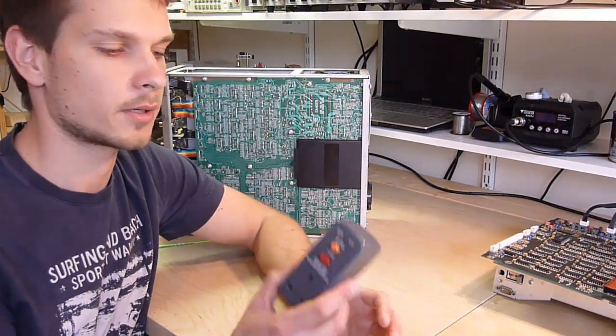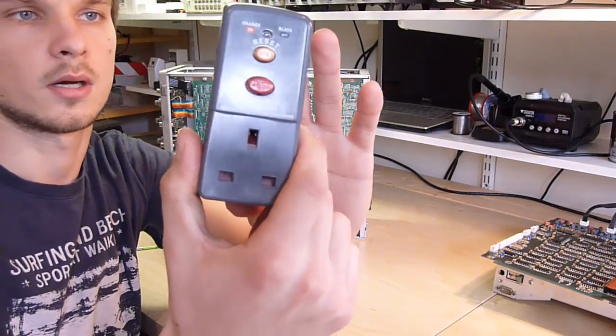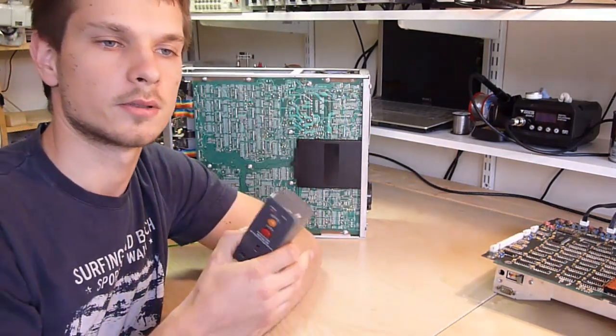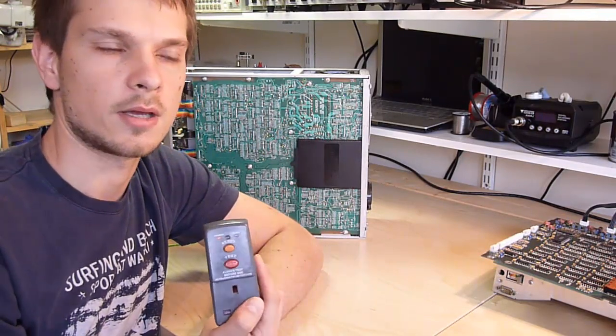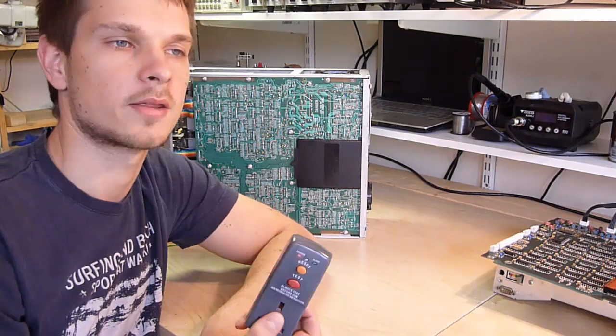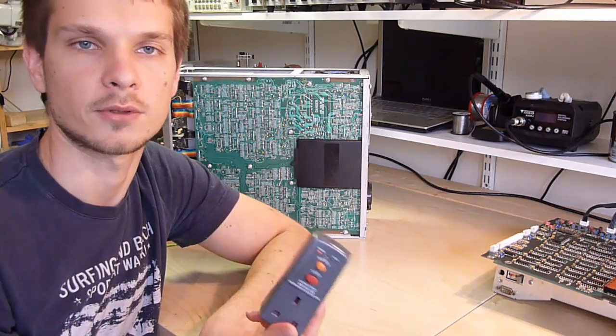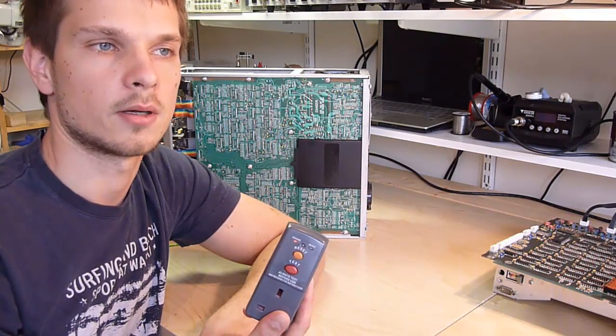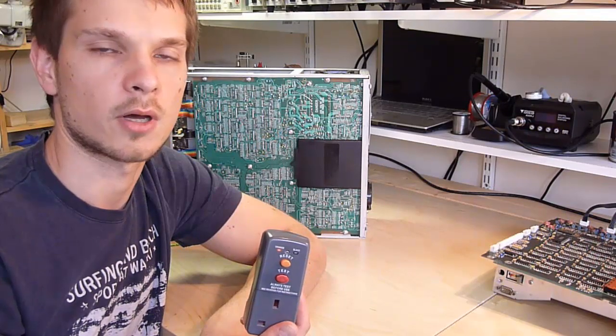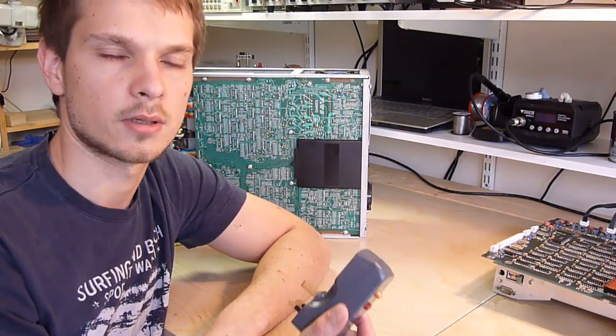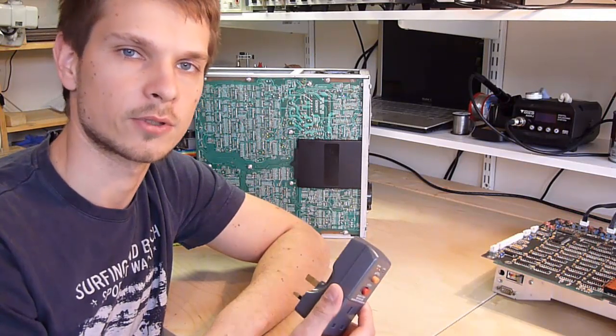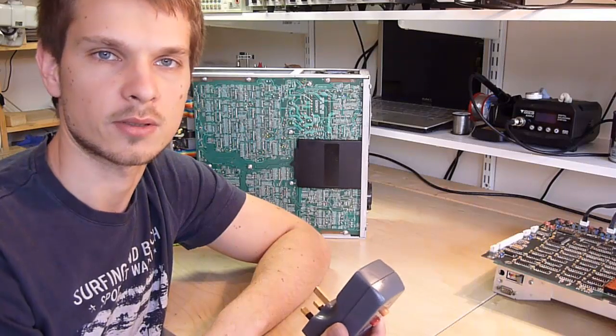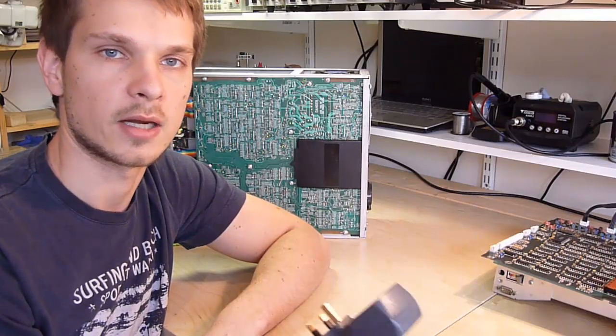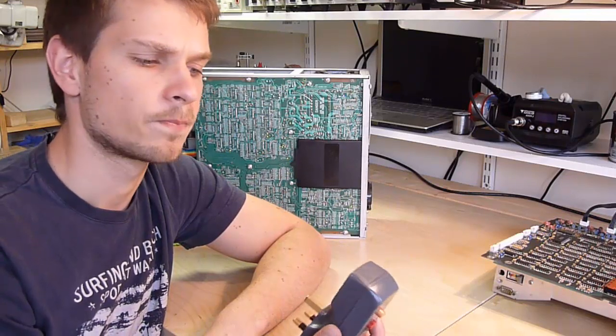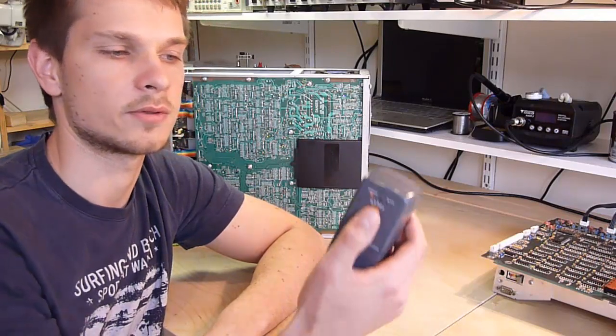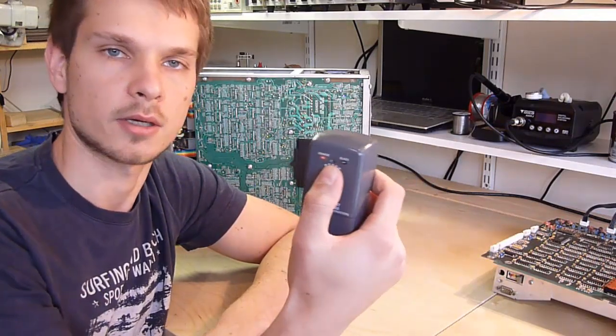Another thing you can do is you can use one of these RCD, which is a residual current device. It will detect if there is any current path apart from the one going from the live to neutral. So if there is a current path, say going from live to earth, it monitors the current going into the circuit through the live and back from the circuit through the neutral. And if there's a difference between the current going through the live and coming back through the neutral of more than 30 milliamps, it will cut off the circuit, and you will have to manually press a reset button to turn the circuit back on.